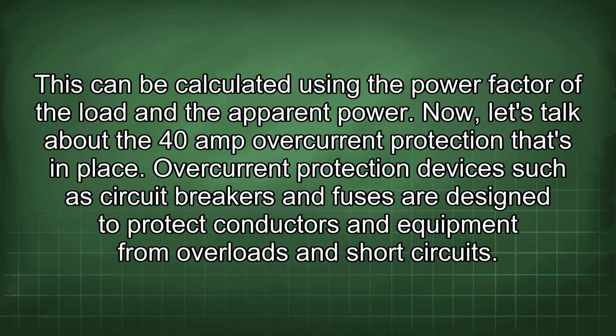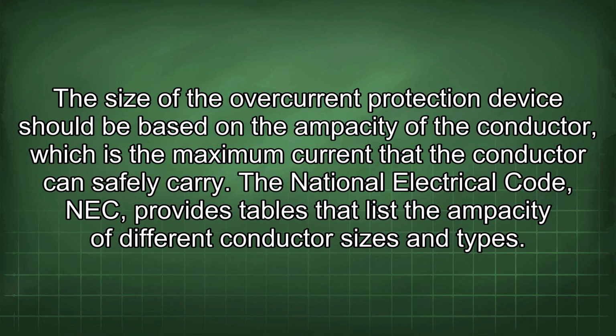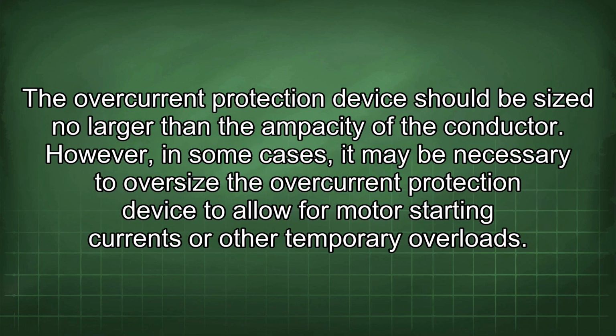Now let's talk about the 40 amp overcurrent protection that's in place. Overcurrent protection devices such as circuit breakers and fuses are designed to protect conductors and equipment from overloads and short circuits. The size of the overcurrent protection device should be based on the ampacity of the conductor, which is the maximum current that the conductor can safely carry. The National Electrical Code, NEC, provides tables that list the ampacity of different conductor sizes and types. The overcurrent protection device should be sized no larger than the ampacity of the conductor.